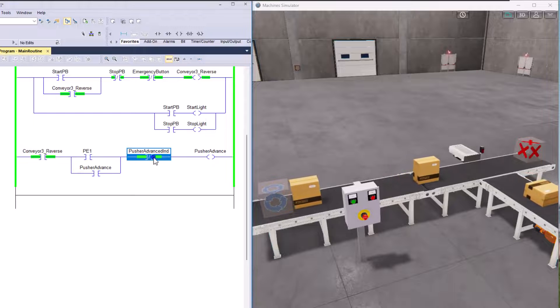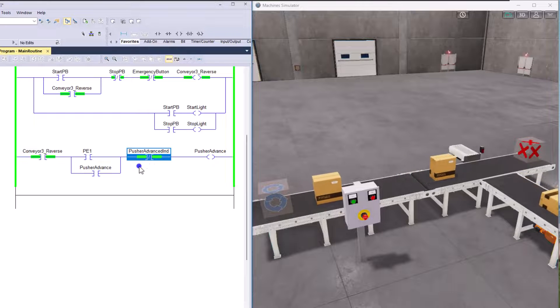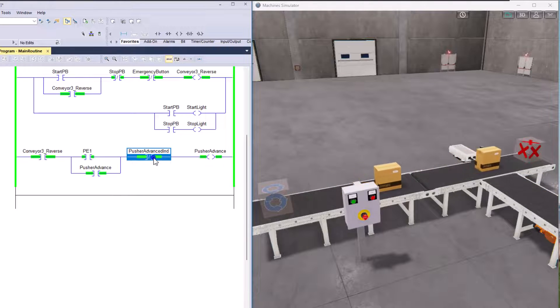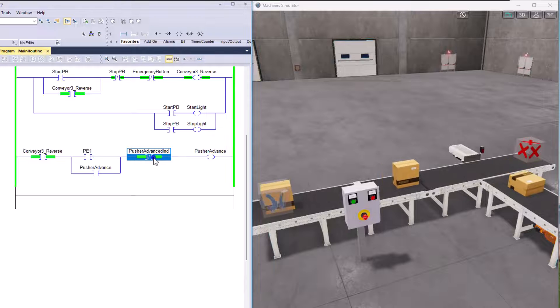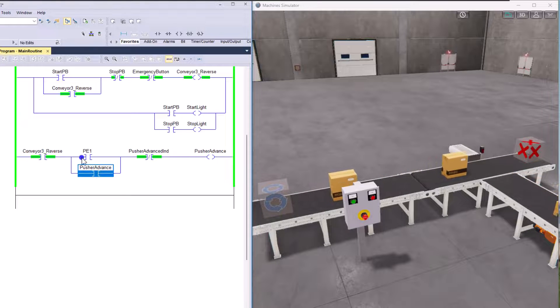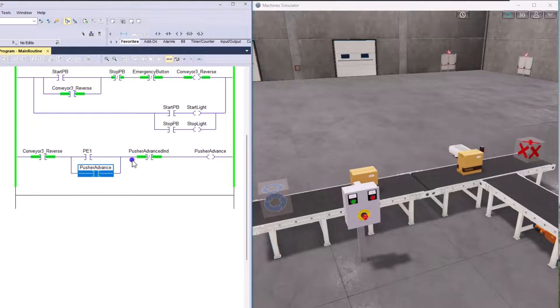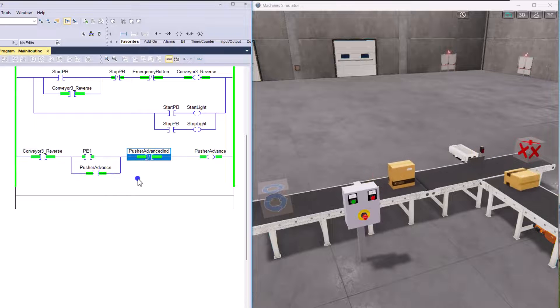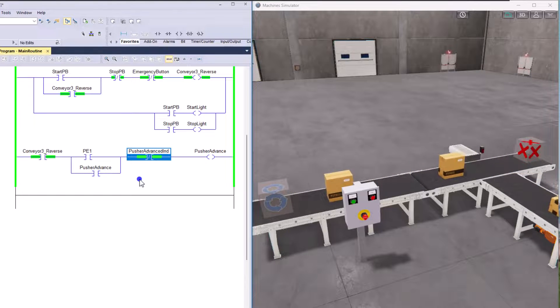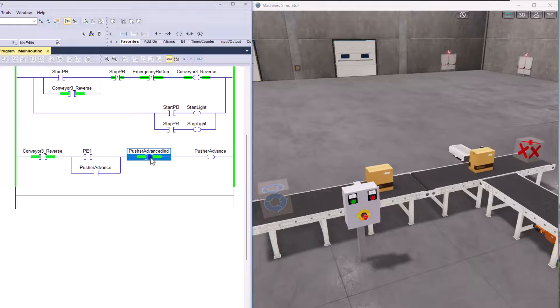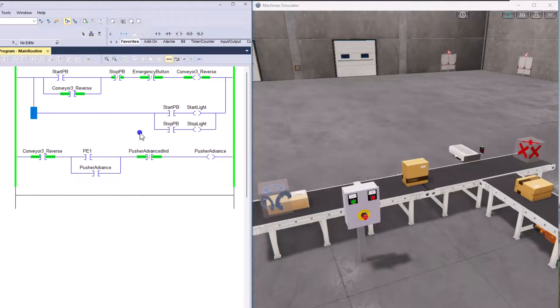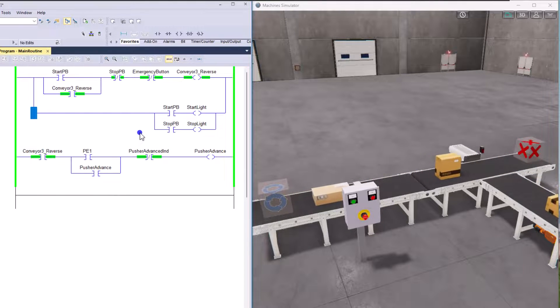So once, you'll see this right here, as soon as it goes out, this bit will go high and then unseal that. So basically we're using seal in circuits again, and then we're unsealing it with a said bit or said function in this case, an inductive prox. And that's basically how that process works.